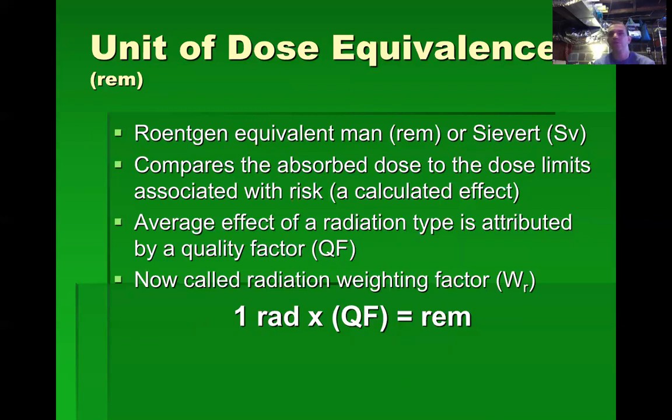You can put detectors inside of phantoms that imitate the human body, and that is one way that is used very commonly. But for convenience, there's nothing easier than picking up an exposure rate meter and characterizing a radiation field based on its ionization of the air. That is something we do for all of our surveys. That's something we do for patient surveys. That is our main method of quantifying radiation.